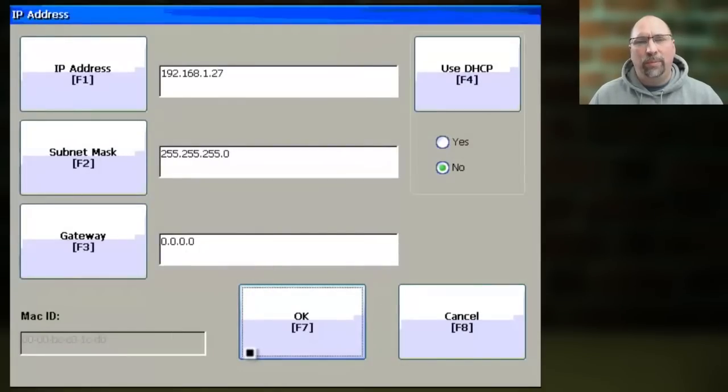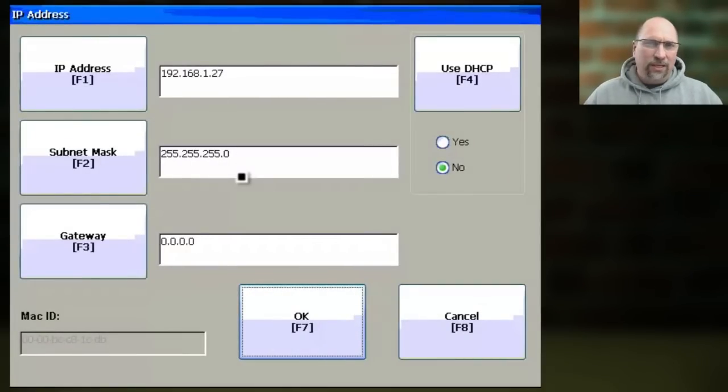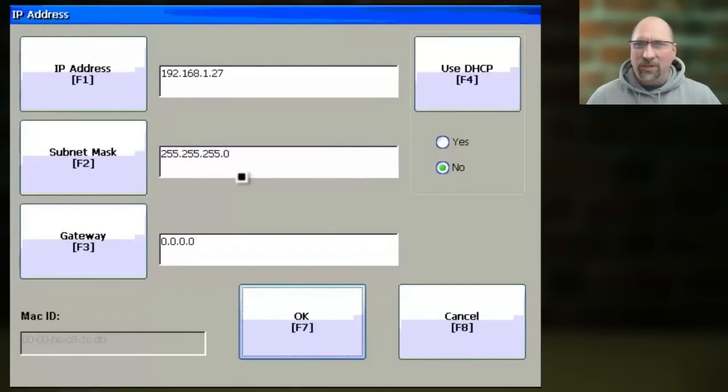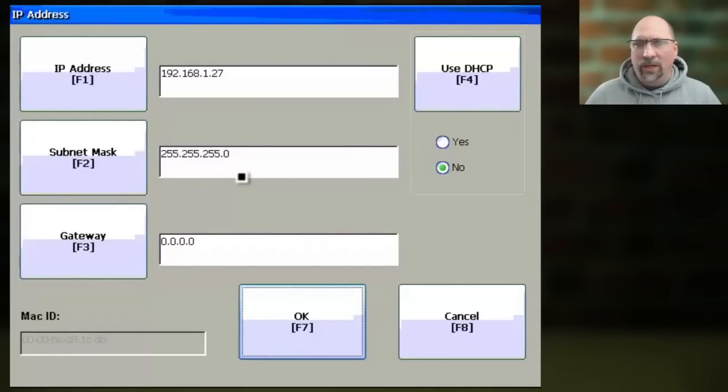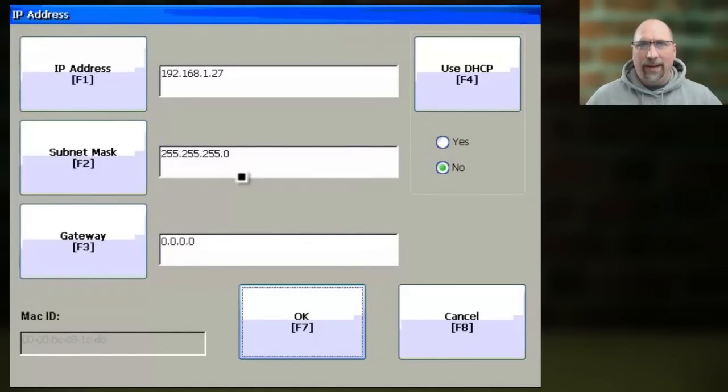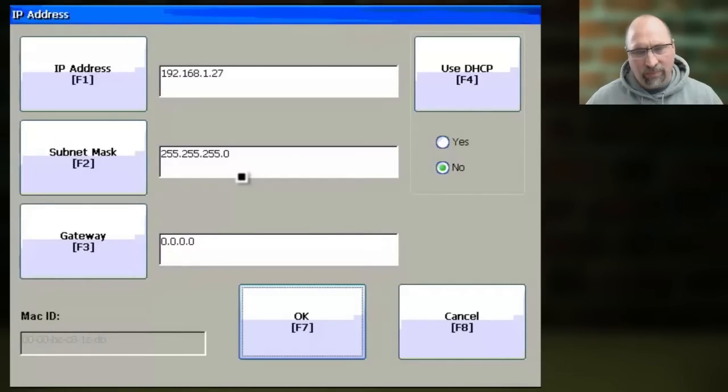Now at a minimum, you're going to need an IP address and subnet mask that's compatible with the same subnet that your PLC or other devices that your PanelView is going to talk to is on. So your PanelView has to sit on the same subnet as the devices it's going to talk to, whether it be a PLC or some other device.